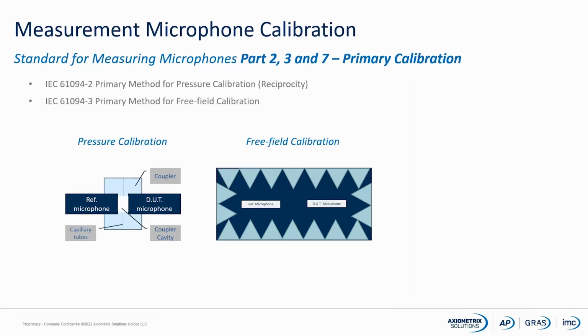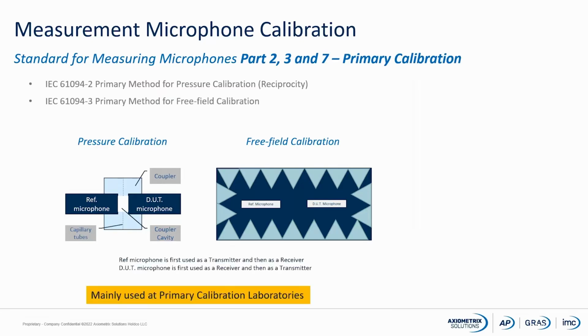We can do exactly the same in a free field environment. The principle is exactly the same. So we have the two microphones pointing at each other, and then we will use one microphone as a source and the other one as a receiver, and then we will do it the other way around and then calculate the sensitivity at the frequency we are testing for the time being. And it is a method which is mainly used in primary calibration laboratories because, as I mentioned before, it is a rather time-consuming process.